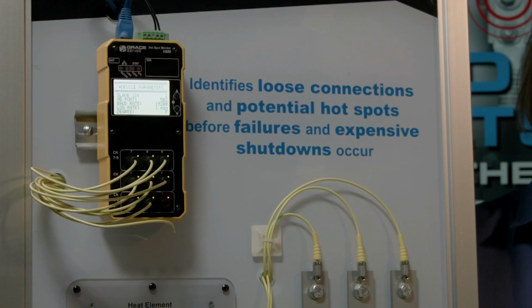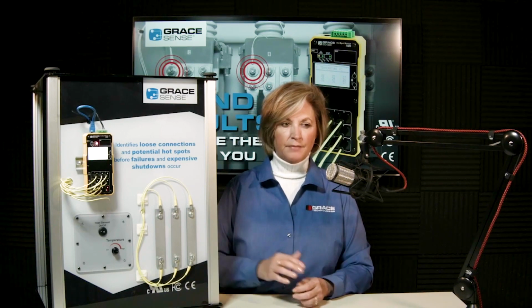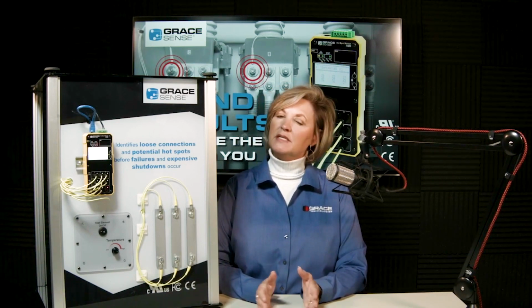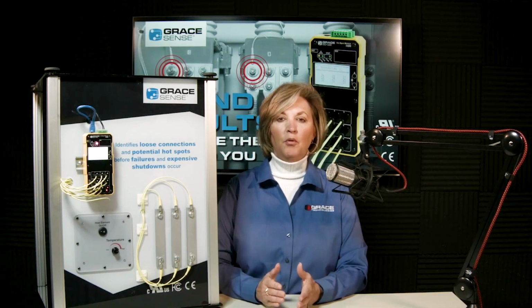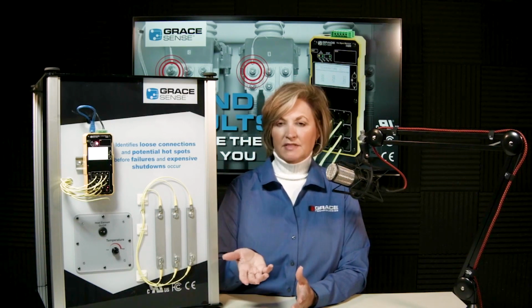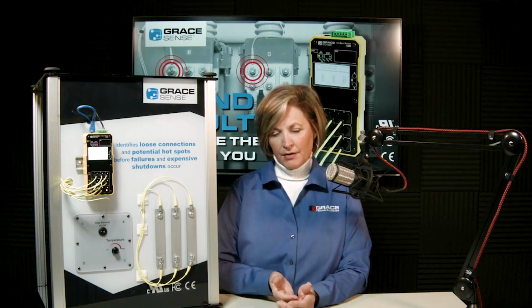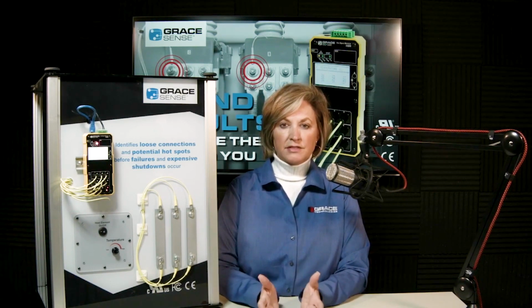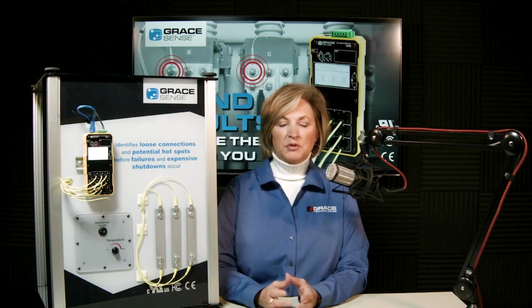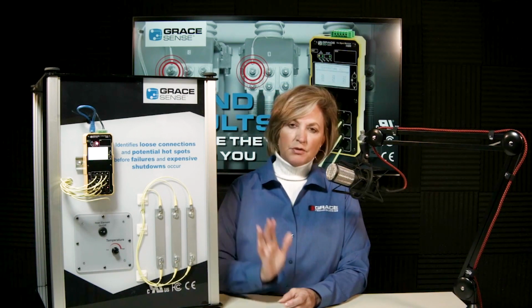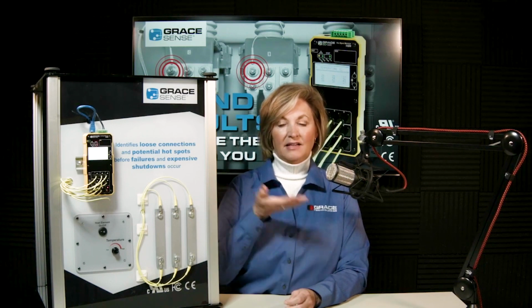So let's talk applications. Obviously, there are a lot of different pieces of equipment that are carrying current. And as we know, increasing current increases the temperature. So what we want to talk about is where the most important points are within different pieces of electrical equipment to make it a viable point to monitor. So I always start out by asking, what do you currently thermal scan? There are many insurance companies that require an annual thermal scan. Some industries that are self-insured maybe do thermal scans every 3 years. However, with the continuous thermal monitoring solution, you will get it continuously. So you'll know on a regular basis what's happening deep inside your asset.